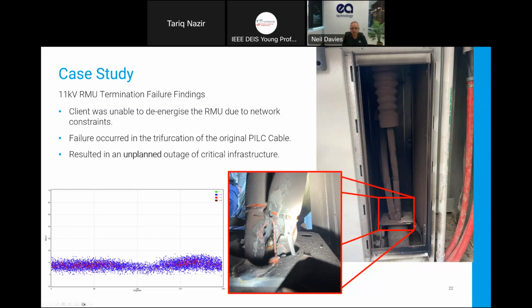So it occurred in the trifurcation of the PILC joint at the bottom here, and we ended up with an unplanned outage of that critical infrastructure. In this particular instance, this is an ultrasonic trace measured in decibel microvolts. It's not a huge level of discharge, but the difficulty with ultrasonic is the level of discharge you find on any one day can be very much changed by the level of humidity in the environment. So on a dry day, you'll get a lower signal than on a humid day. So you have to be very careful for that. And trending surface discharge as it moves towards failure is also very difficult, if not impossible to do.